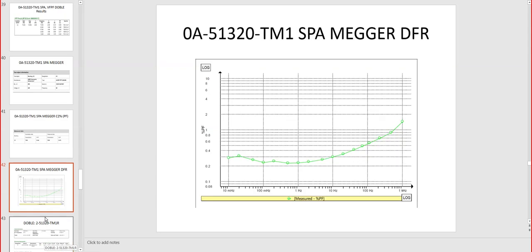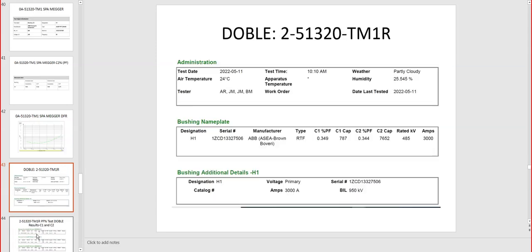And Megger on C2, here are the values in power factor, capacitance, nameplate data on the left, and measured data on the right, and that is for C2. So H1 looks pretty close to the manufacturer data. However, DFR, dielectric frequency response, for the same H1 bushing high voltage, we can see the curves here, from 10 millihertz to 1 kilohertz.